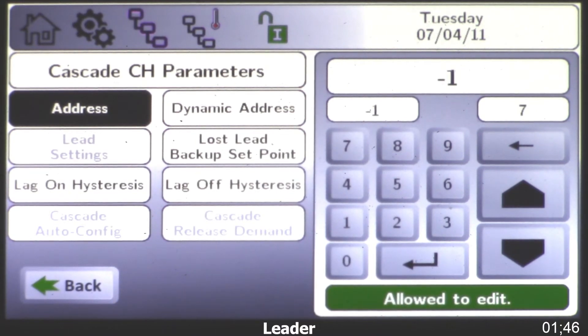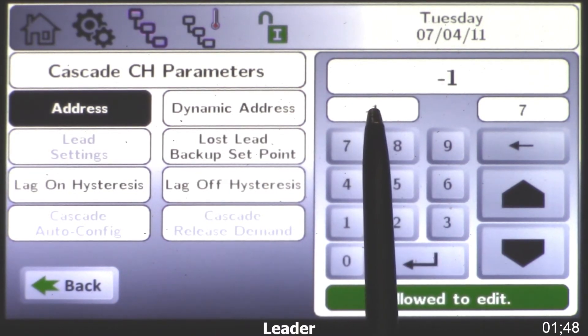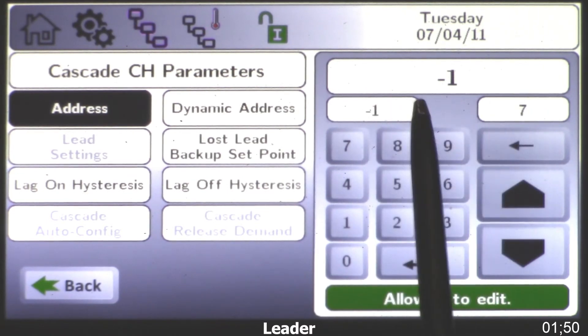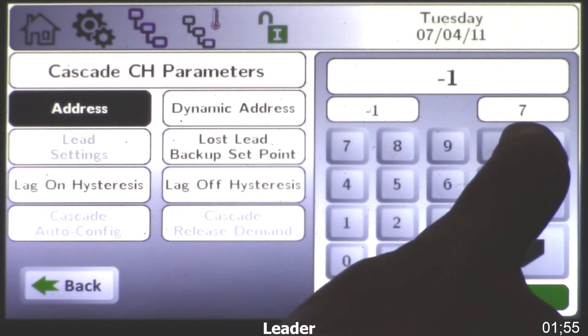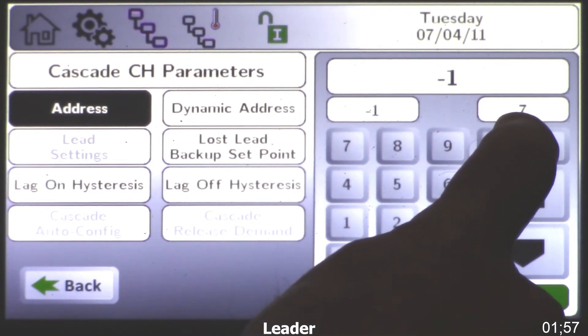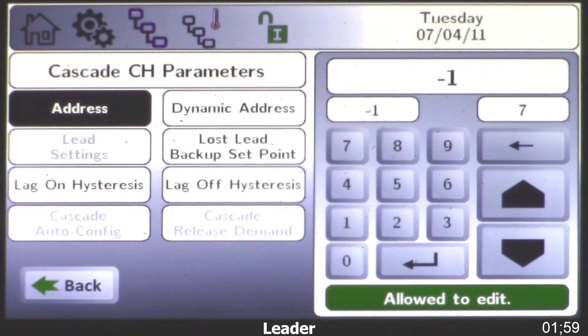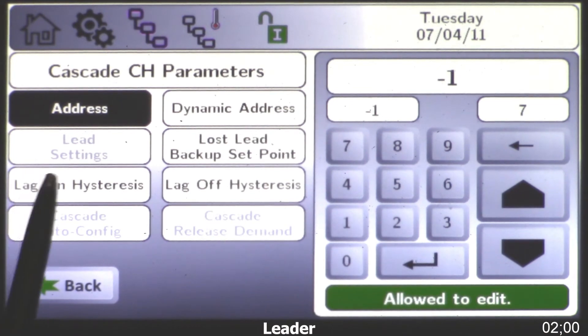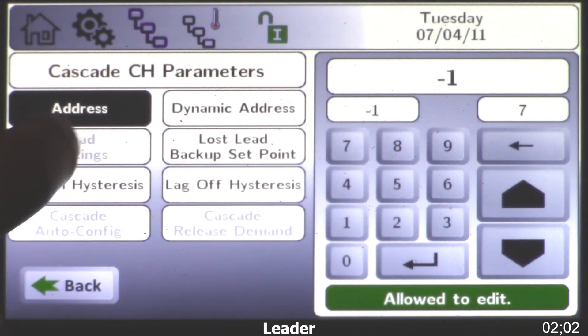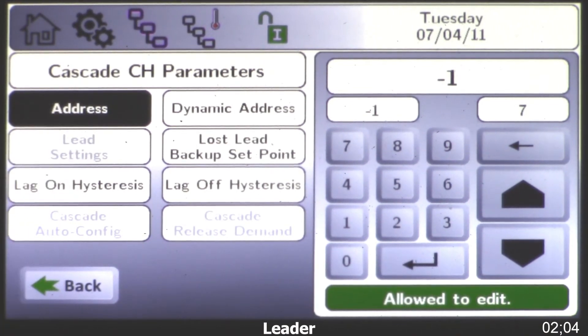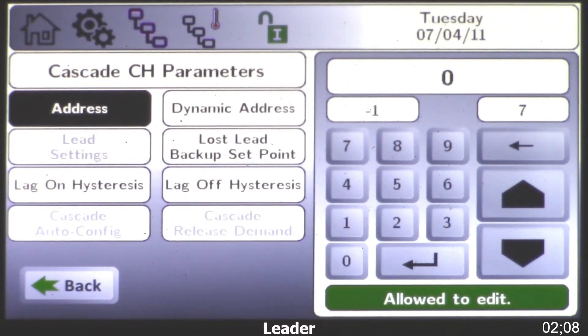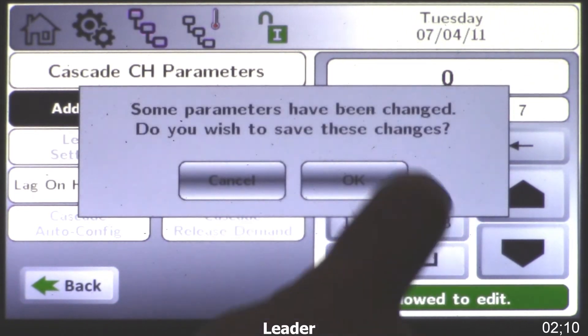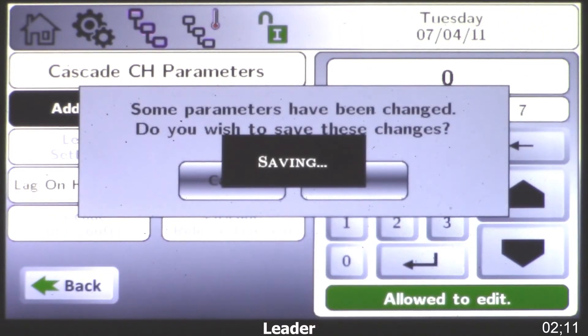Next I'm going to come back to address — this is the lead boiler. The range is minus one to seven and all of the boilers will be defaulted for minus one. Your lead boiler becomes zero. Before I type that in, I want to point out that lead settings is in light gray and we can't make any changes there yet. However, when I choose the leader as zero, enter, click OK, our lead settings will become available.